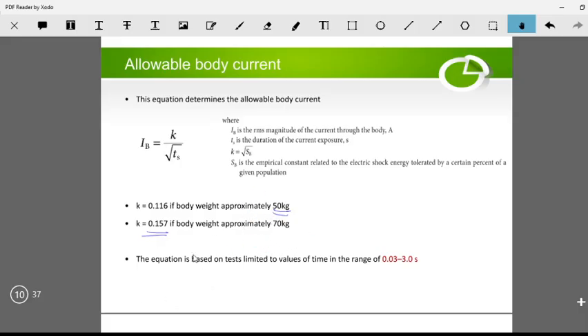The equation is based on test limits for time values in the range of 0.03 to 3 seconds, so this equation is valid for TS between 0.03 and 3 seconds. There are other equations defined for different, larger time ranges, but they all narrow down to give similar IB results within this range.